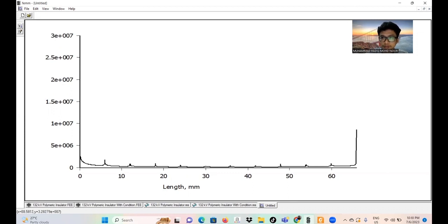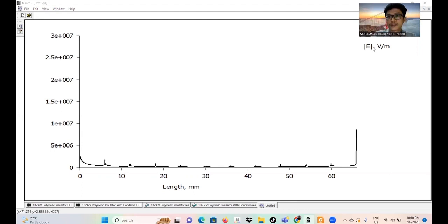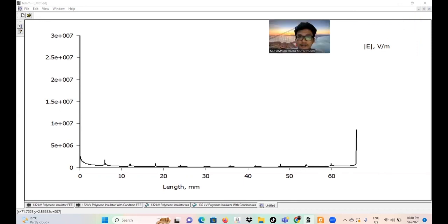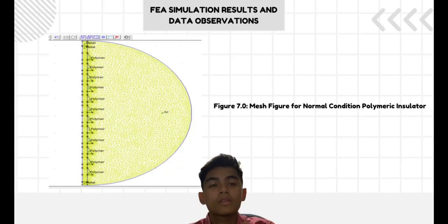5 kilovolt per meter. As you can see over here, the field is the same as voltage per meter. So after it reaches 60 mm of the length of the alternate shed polymeric insulator prototype, we can see that it carries the value of 5 kilovolt per meter. So this is the graph for wet condition. So let's move to contaminated condition.